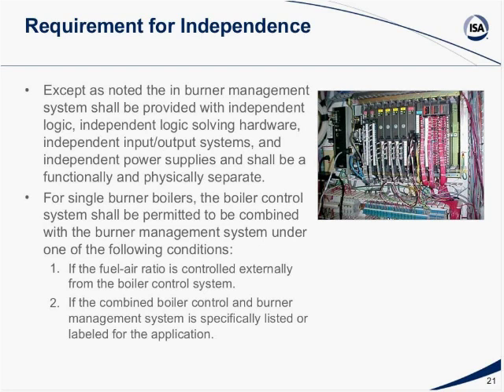The other thing that has become a real big issue in the industry is the independence of your control system and your safety system, whether it be burner management or any other process control safety system. Except as noted, the burner management system shall be provided with independent logic solving hardware, input-output systems, and independent power supplies, and shall be functionally and physically separate. For single burner boilers, the control system shall be permitted to be combined with the burner management system under one of the following conditions. In other words, under most conditions they need to be totally independent. But under a couple of conditions, you do not have to keep them independent, and they can be built into one system, provided it meets the safety requirements.